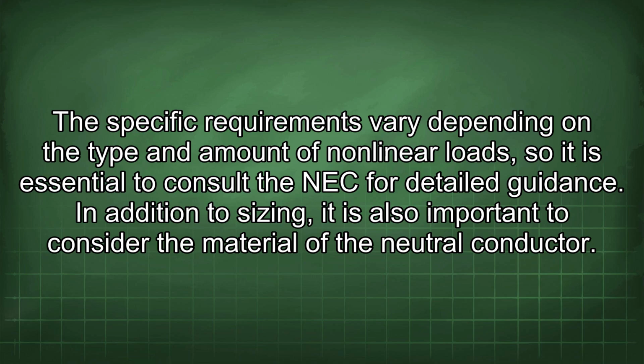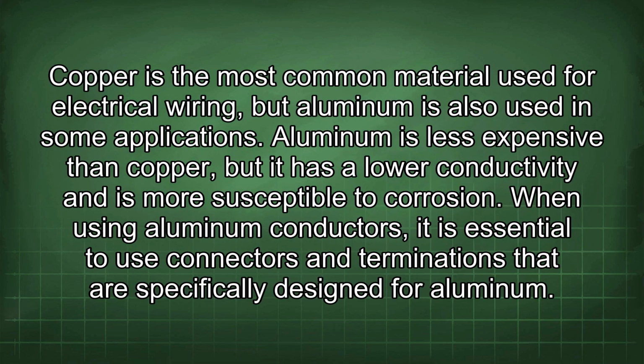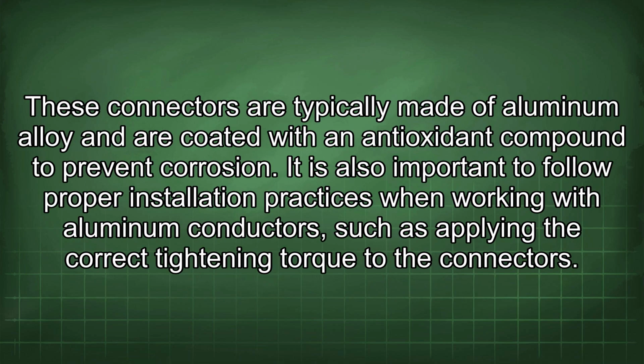In addition to sizing, it is also important to consider the material of the neutral conductor. Copper is the most common material used for electrical wiring, but aluminum is also used in some applications. Aluminum is less expensive than copper, but it has a lower conductivity and is more susceptible to corrosion. When using aluminum conductors, it is essential to use connectors and terminations that are specifically designed for aluminum. These connectors are typically made of aluminum alloy and are coated with an antioxidant compound to prevent corrosion.